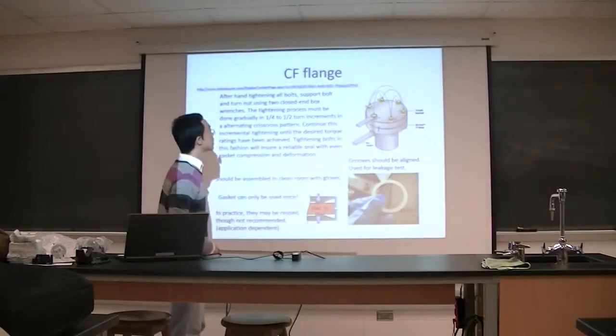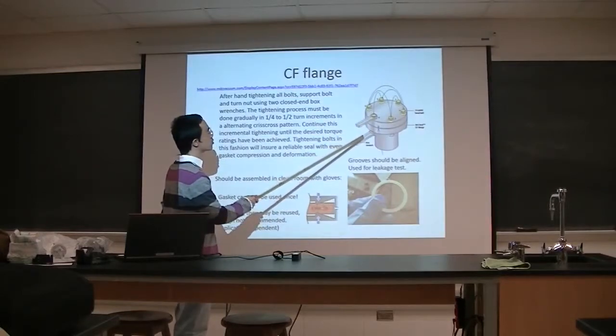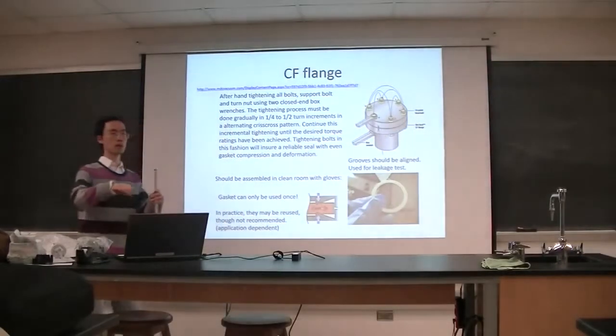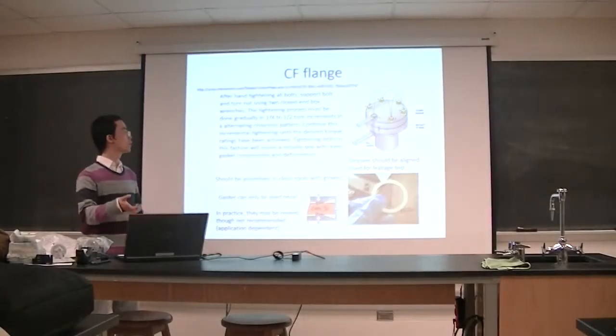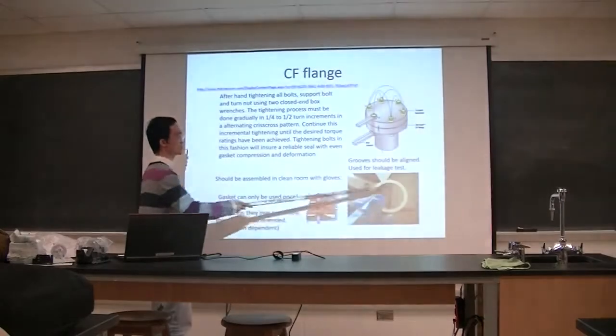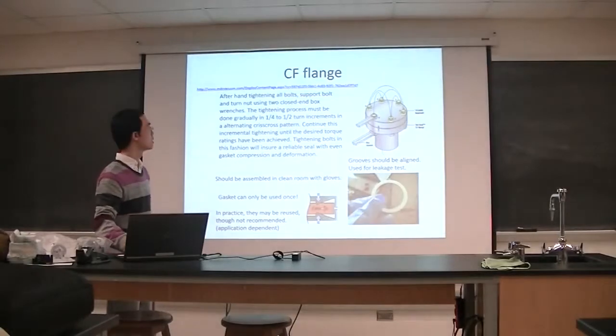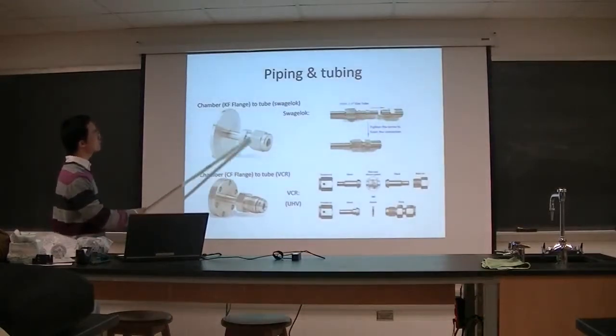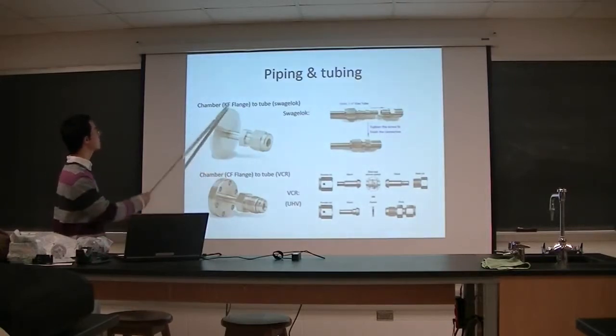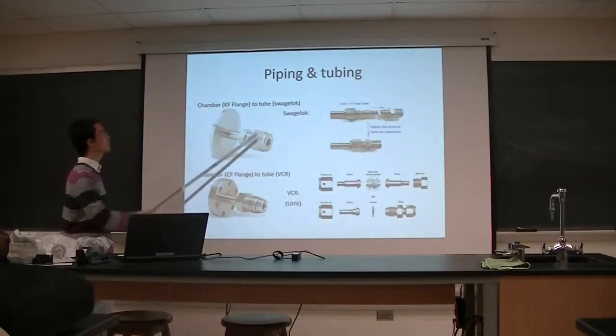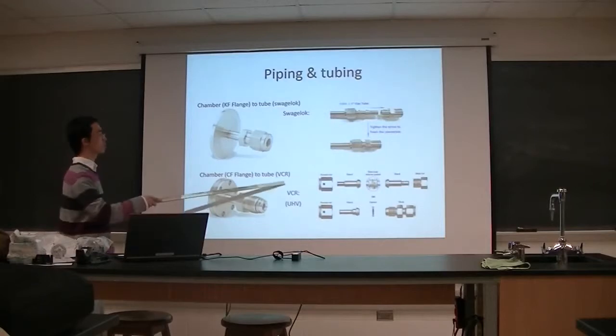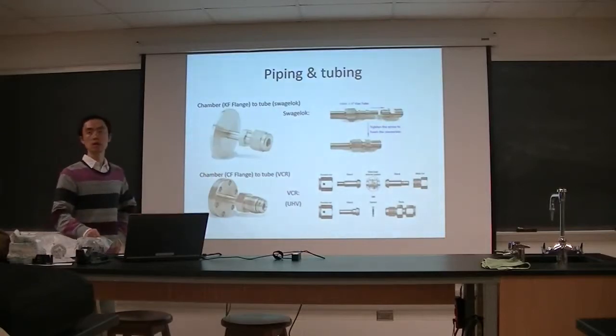When tightening the screws, you need to follow a specific sequence — do not tighten all screws on one side first, then the other. This creates unbalanced pressure on the gasket, and when you open the chamber you will see the gasket is not evenly pressed. For connecting chambers, pipes, and tubes, we have CF and KF flanges on the chamber side. On the tube side, there are two standards: Swagelok and VCR. VCR is for ultra-high vacuum, while Swagelok is very convenient for other applications.